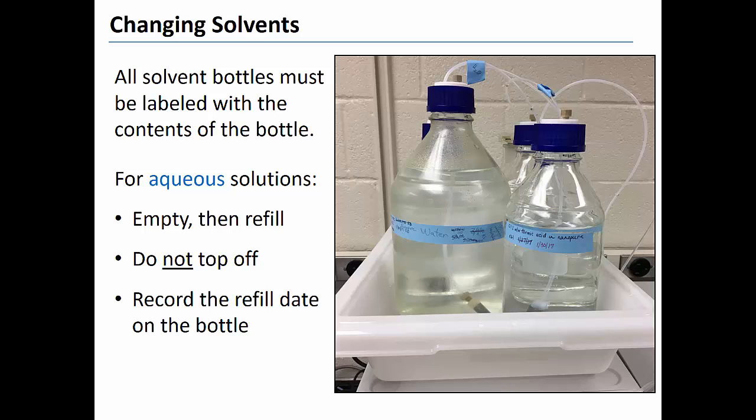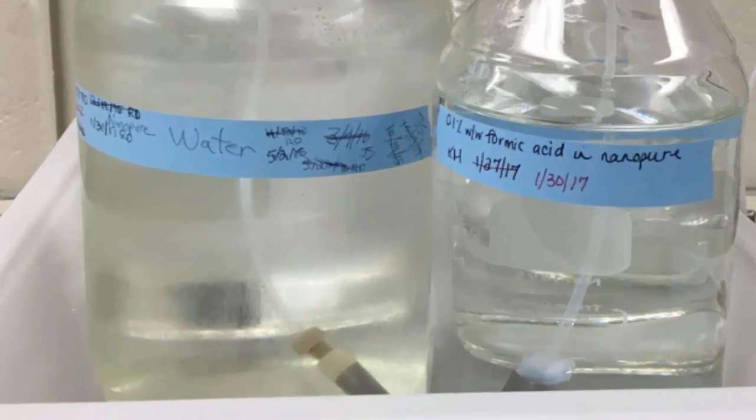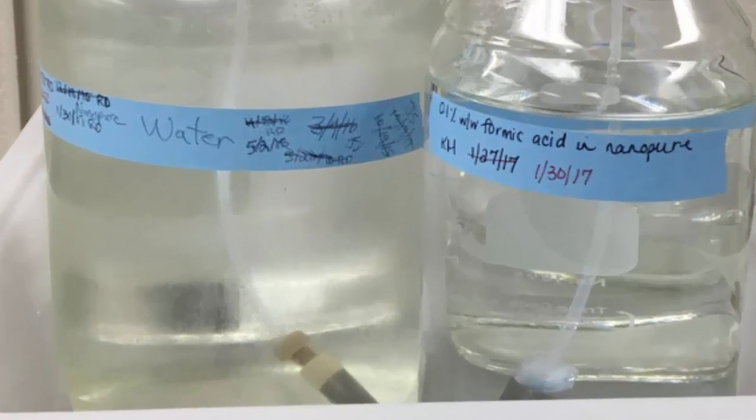As such, aqueous solutions should be completely replaced on a regular basis. To help all users keep track of the age of mobile phase components, please record the refill date on the bottle for all aqueous solutions.